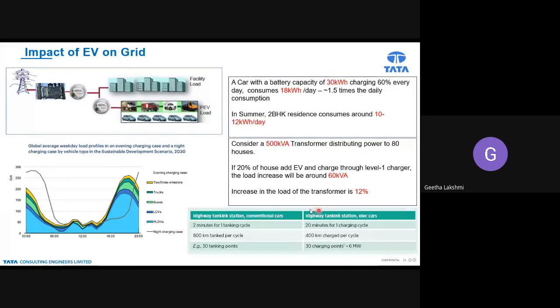So if we take a distribution transformer of a locality, say a 500 kVA transformer distributing power to 80 houses, and if 20% of the houses add EVs charged through a level 1 charger, the load will increase to around 60 kVA, which is around 12%.